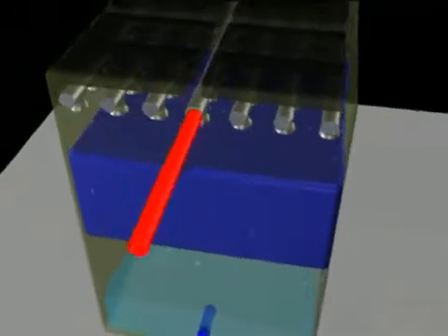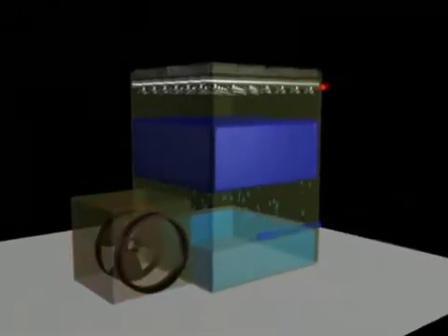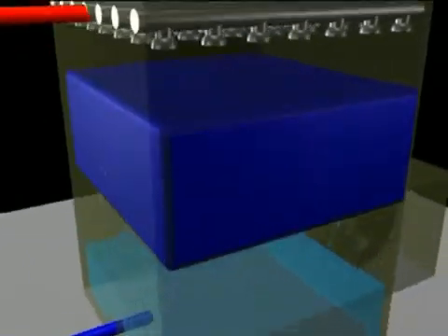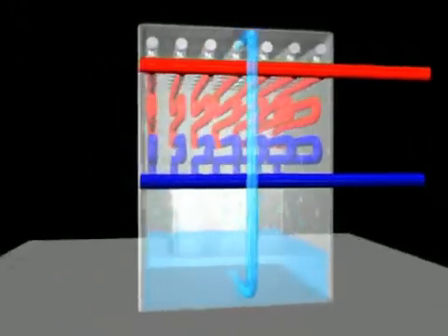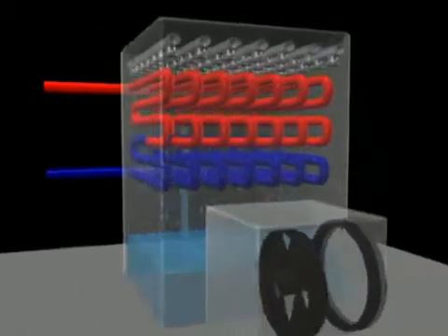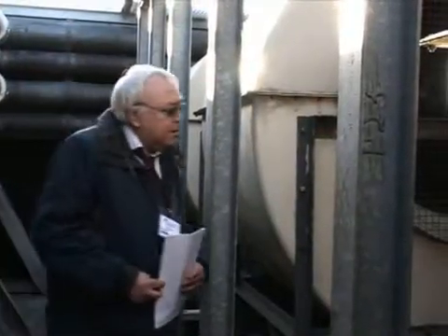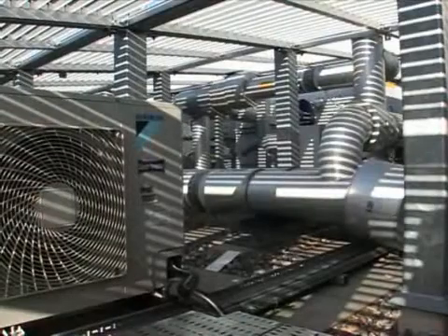An open circuit cooling tower transfers heat from water by direct contact between that water and a stream of air. This process causes some water to evaporate, which removes heat and cools the remaining water before it is collected in the tower's cold water basin or pond. A closed circuit cooling tower or evaporative condenser cools a fluid by passing it through a bundle of metal tubes. These are cooled by contact with water passing over them and against a stream of air that also causes some water to evaporate. As air is forced or drawn through the cooling tower, it captures dirt which can be deposited in the water, which along with dissolved solids concentrated by evaporation provides an ideal environment for Legionella to grow.